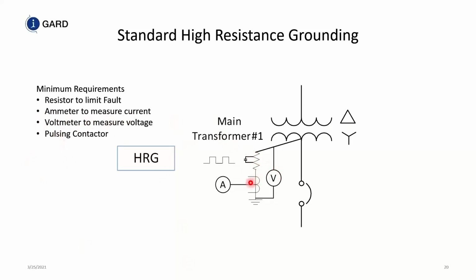You could put an ammeter to determine whether you have fault current in that return path. Because remember, when you have a ground fault on a resistance grounding system, all ground fault current must return back to the source. So by putting a CT right here, we're measuring all the return current that comes back to this point and back to the transformer. You could put a voltmeter on here to measure the voltage across the neutral to ground bus and the pulsing contact.